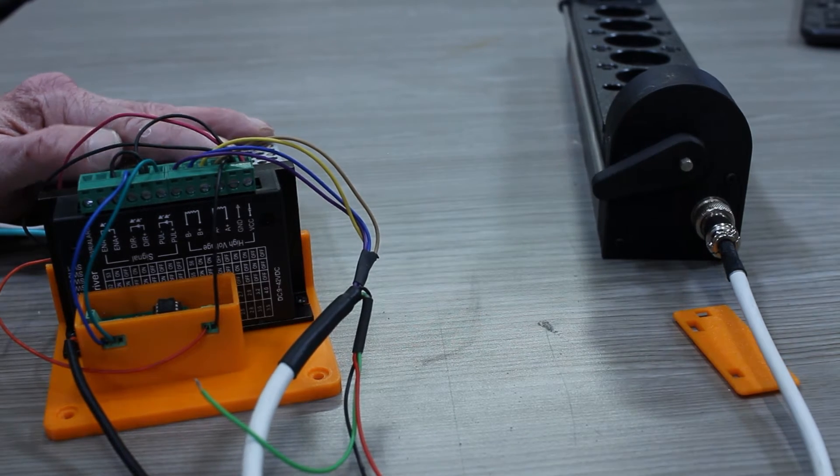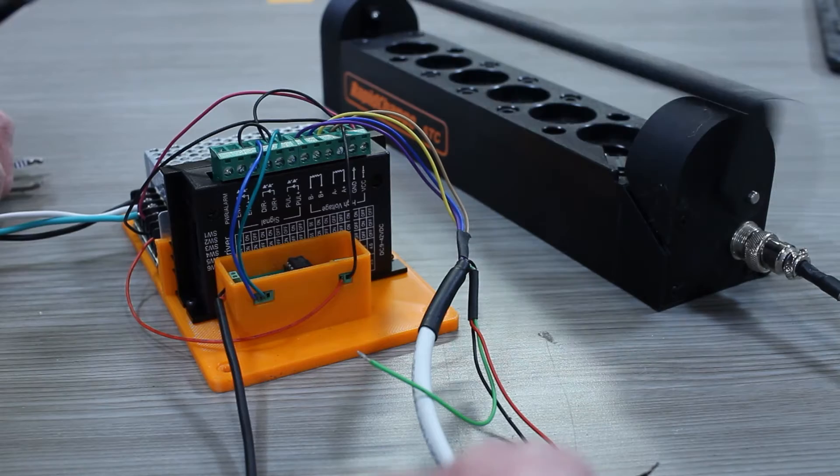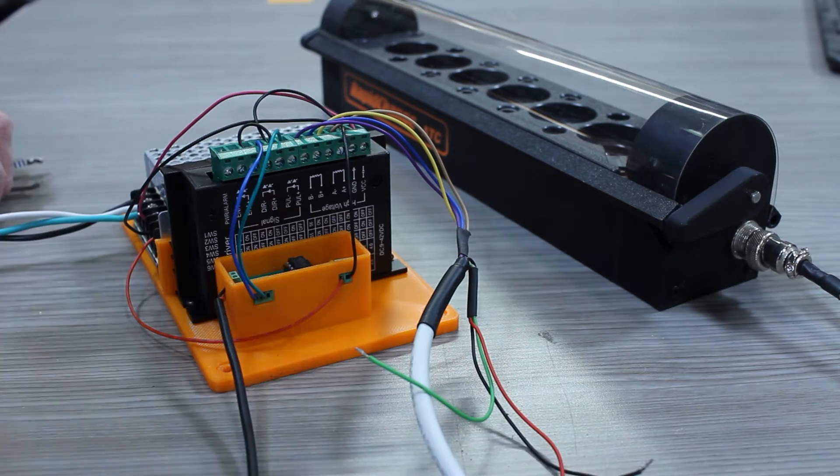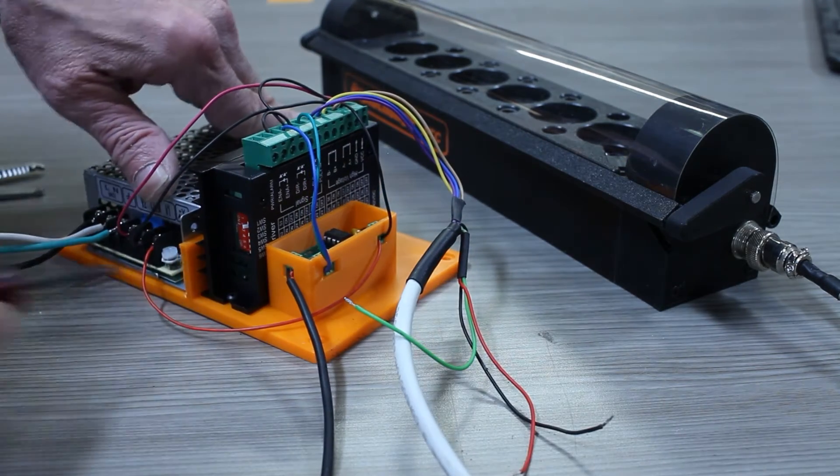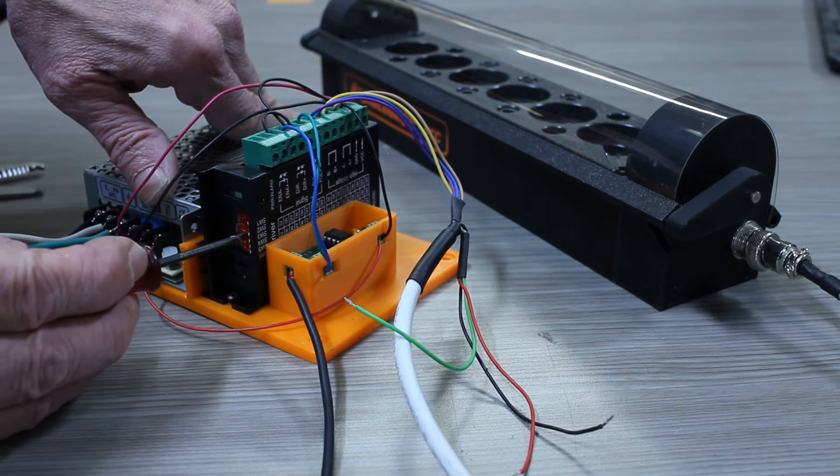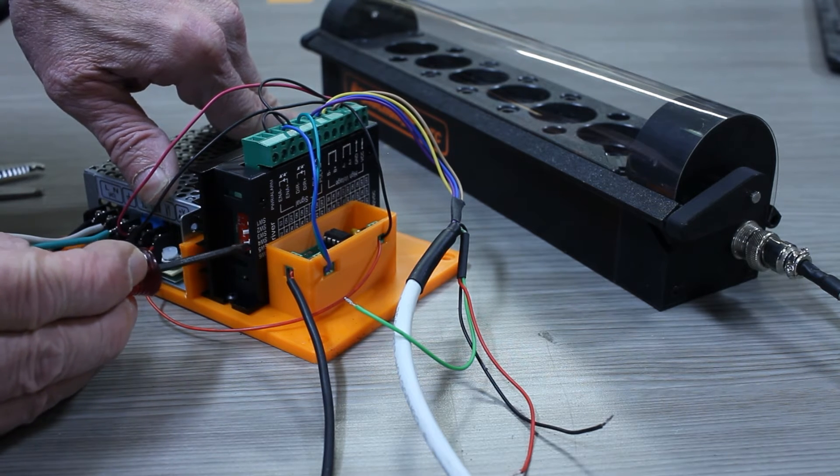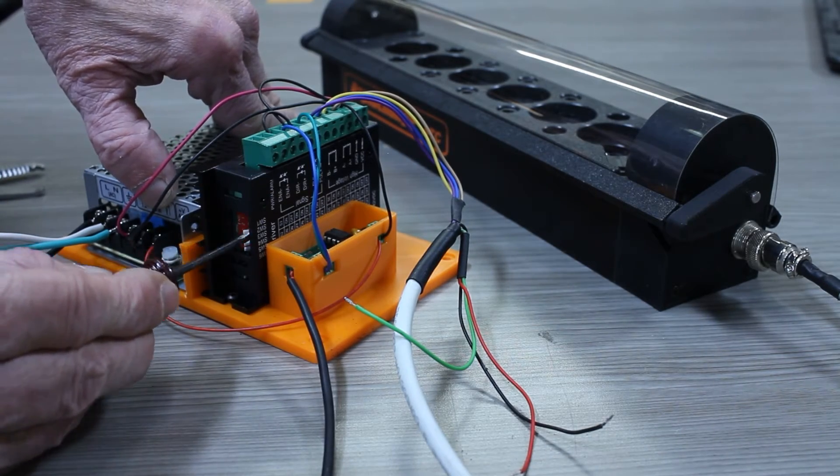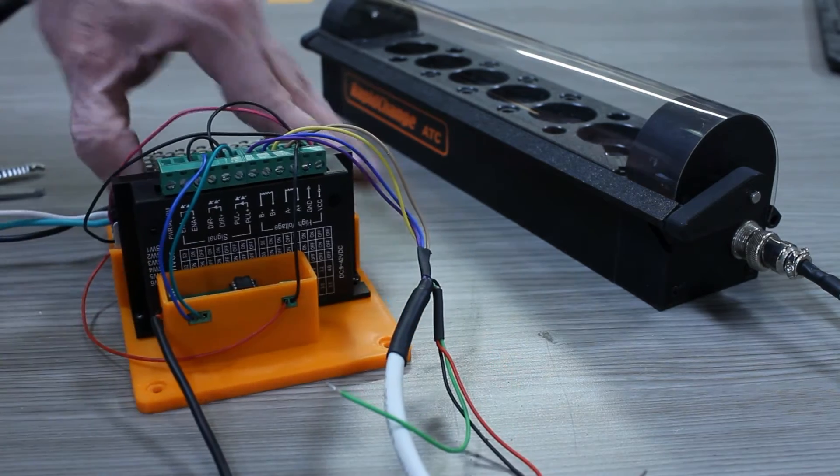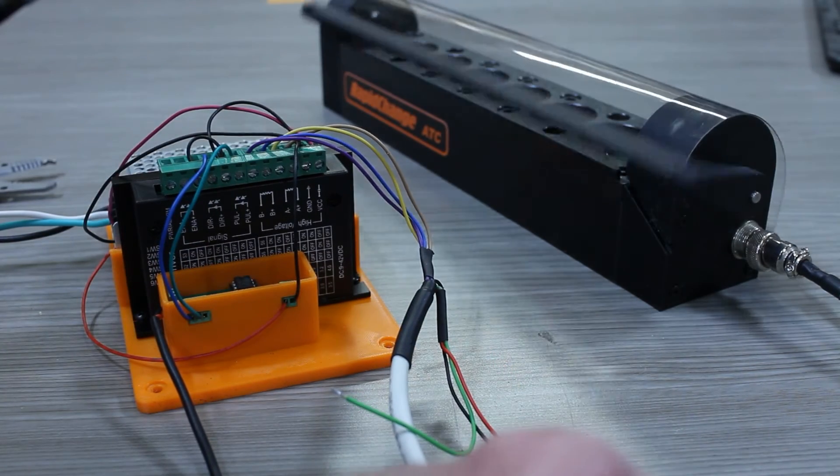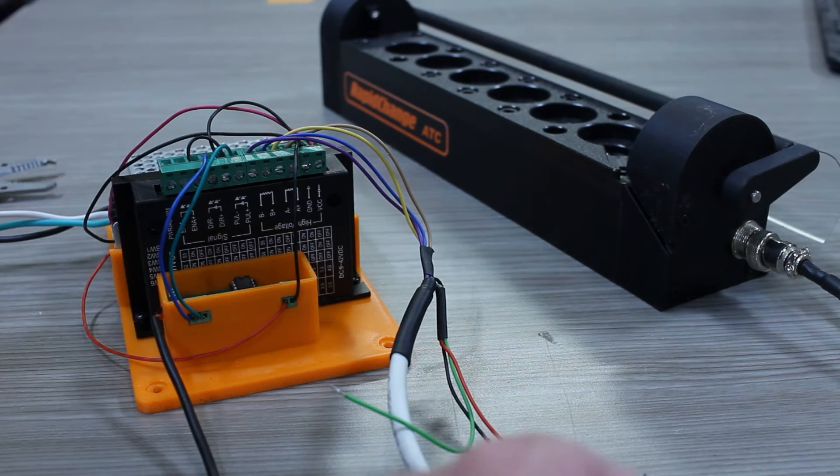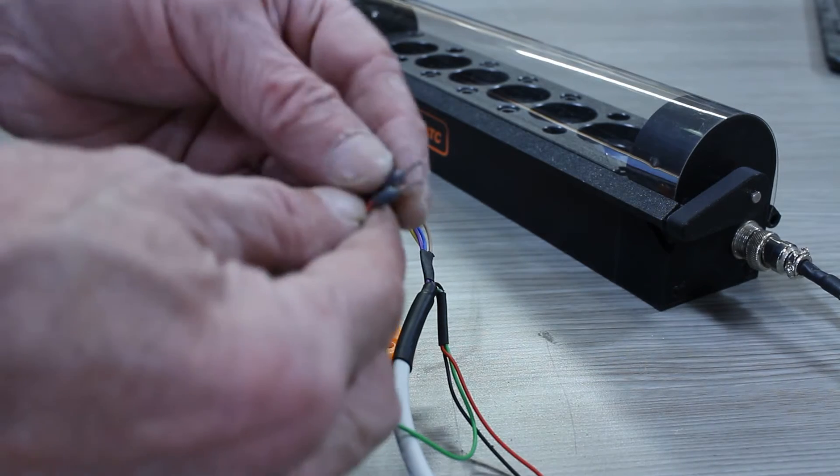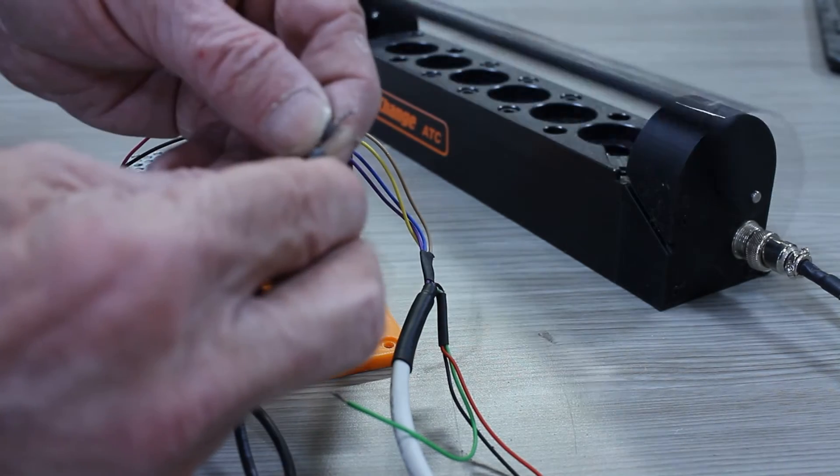Why is it going so far? Oh, I know why, because I don't have a dust cover. That is not right. And I see our dip switches are not set right. So the dip switches want to be three, five, and six down. Three, five, and six down. The rest of them up. And there we go. That's what we want. So it's a simple matter of opening and closing the circuit. Operates the dust cover.